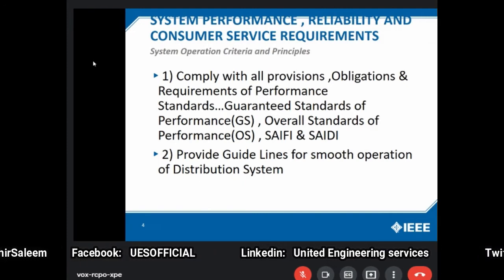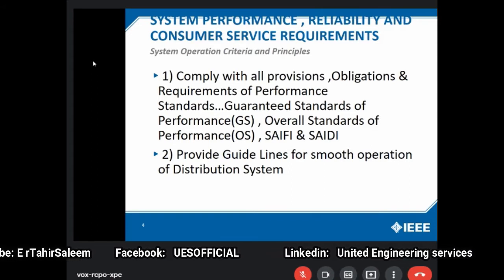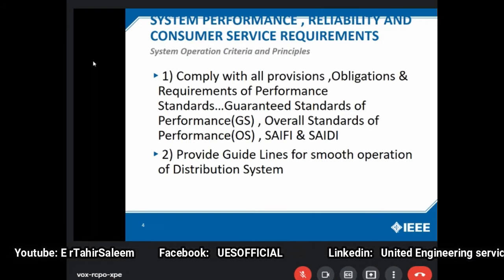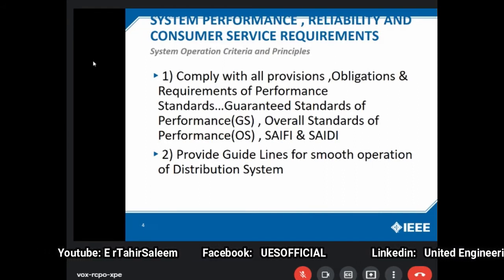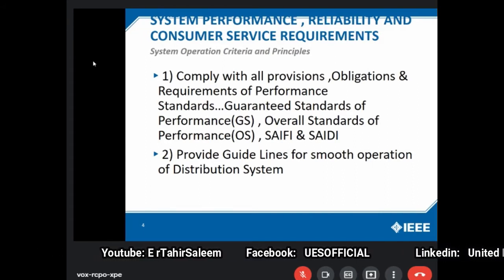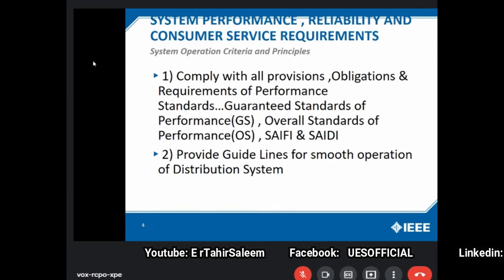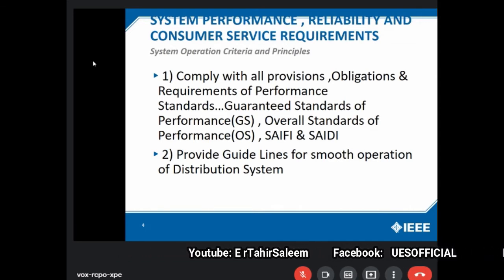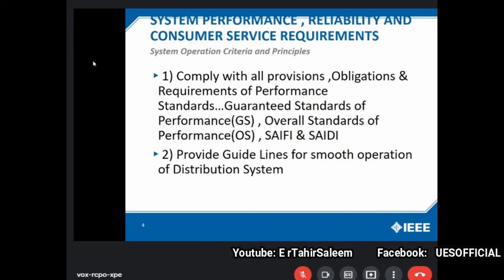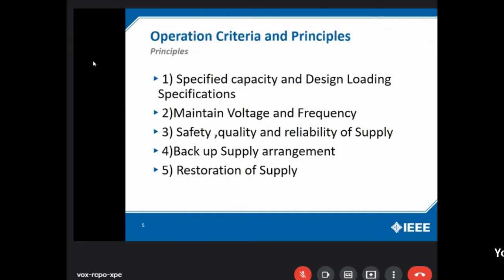And above all, the overall performance of the distribution company can be gauged in terms of the SAIFI and the SAIDI. SAIFI is System Average Interruption Frequency Index, and SAIDI is System Average Interruption Duration Index. This is a separate topic, and that can be covered separately as a whole subject. And the other one is that they provide guidelines for the smooth operation of the distribution system. So let us review what this means for us.